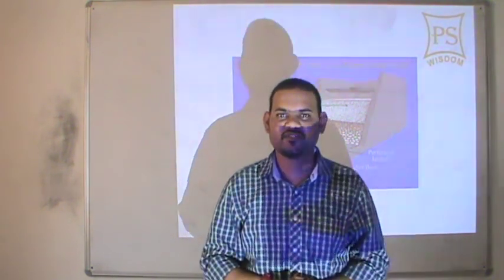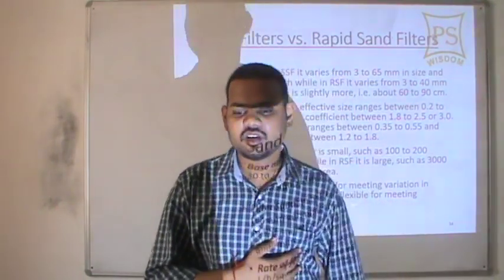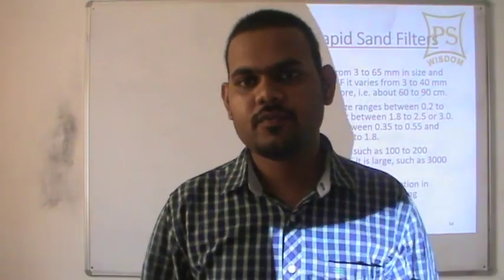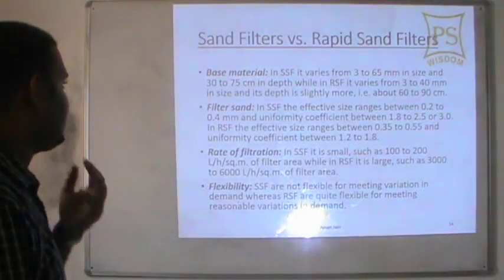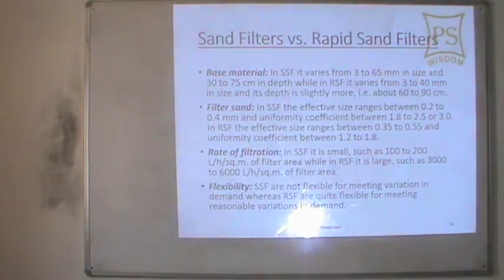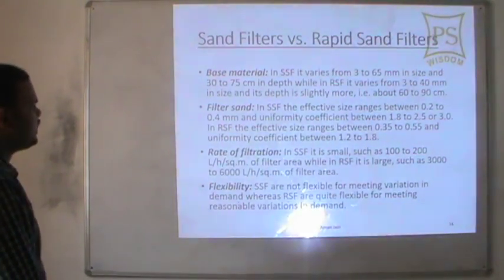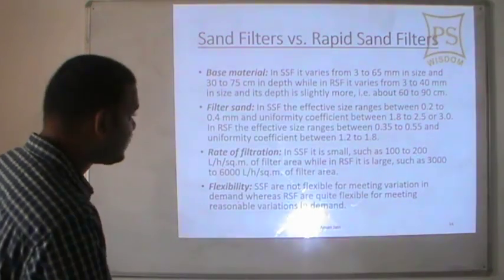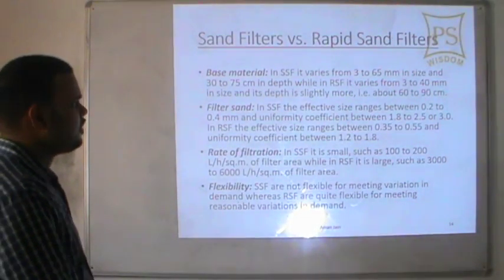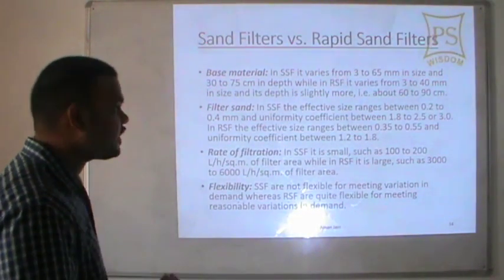Let's compare rapid sand filter (RSF) and slow sand filter (SSF) on several points. For base material: in SSF, gravel varies from 3 to 65 mm in size and 30 to 75 cm in depth; in RSF it varies from 3 to 40 mm in size and depth is 60 to 90 cm — so RSF has smaller gravel size but greater depth. For filter sand: in SSF, effective size ranges from 0.2 to 0.4 mm and uniformity coefficient from 1.8 to 2.5 or 3.0; in RSF, effective size ranges from 0.35 to 0.55 mm and uniformity coefficient from 1.2 to 1.8.